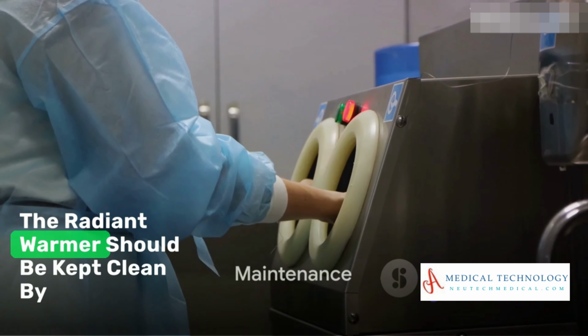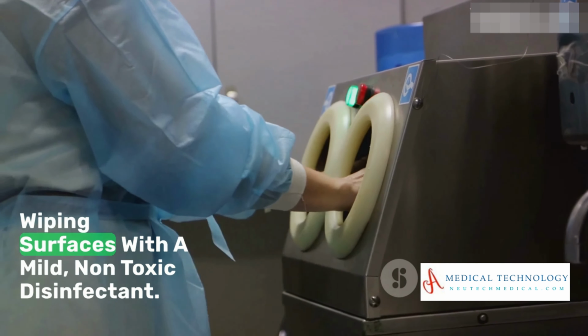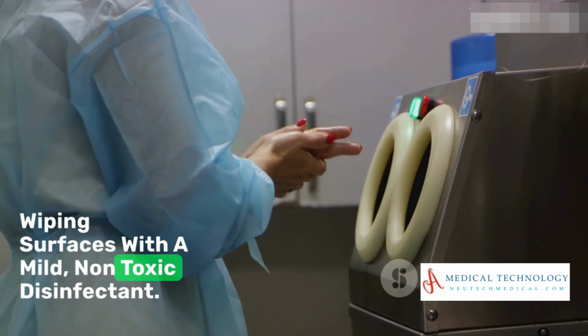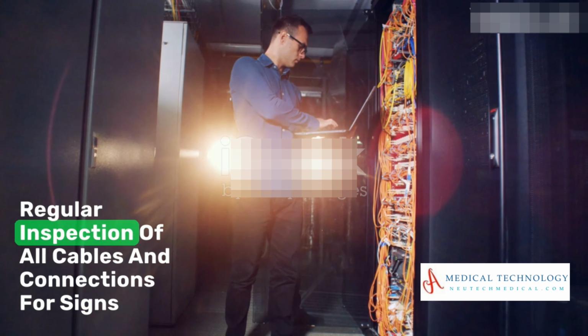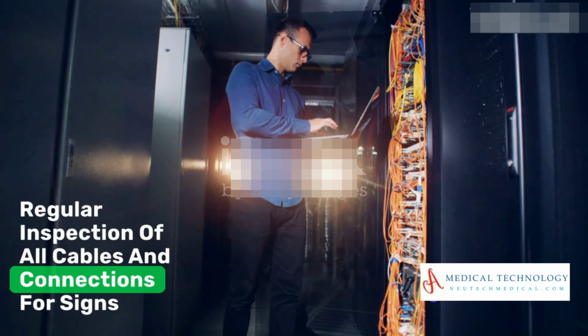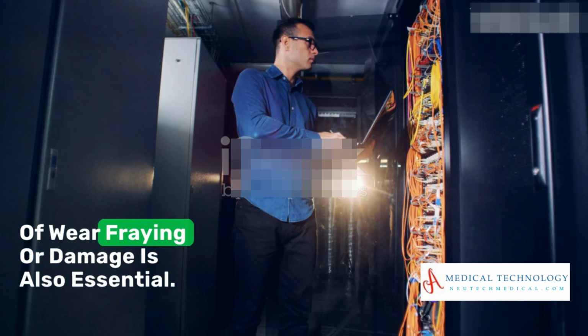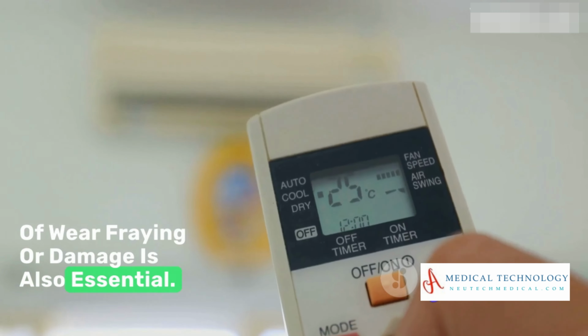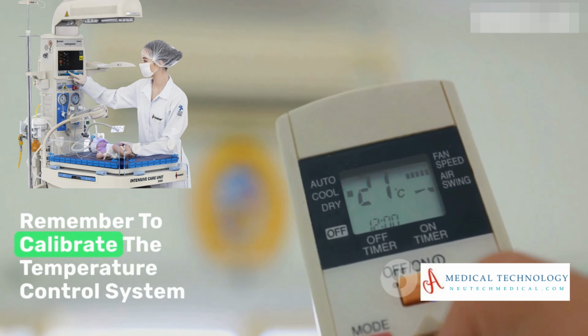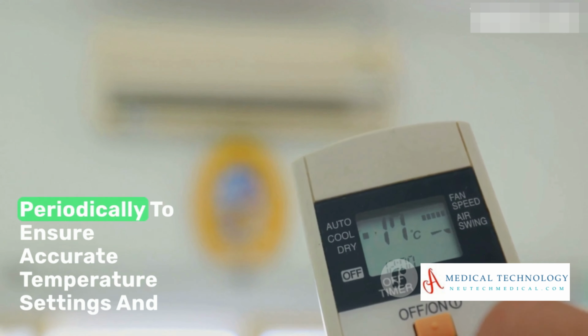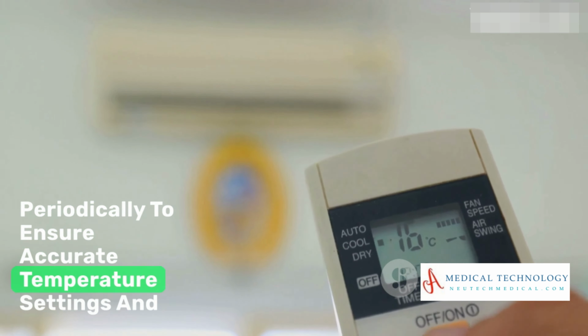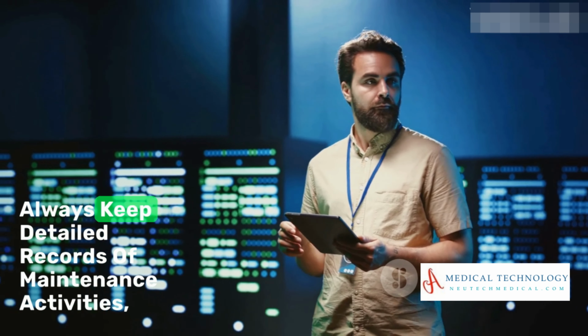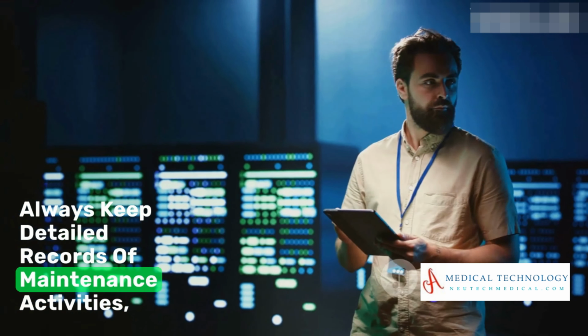The radiant warmer should be kept clean by wiping surfaces with a mild, non-toxic disinfectant. Regular inspection of all cables and connections for signs of wear, fraying, or damage is also essential. Remember to calibrate the temperature control system periodically to ensure accurate temperature settings, and always keep detailed records of maintenance activities, repairs, and any replacements made.